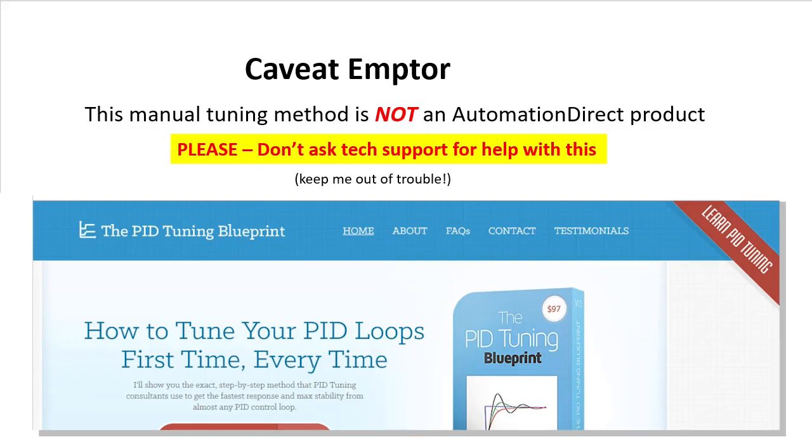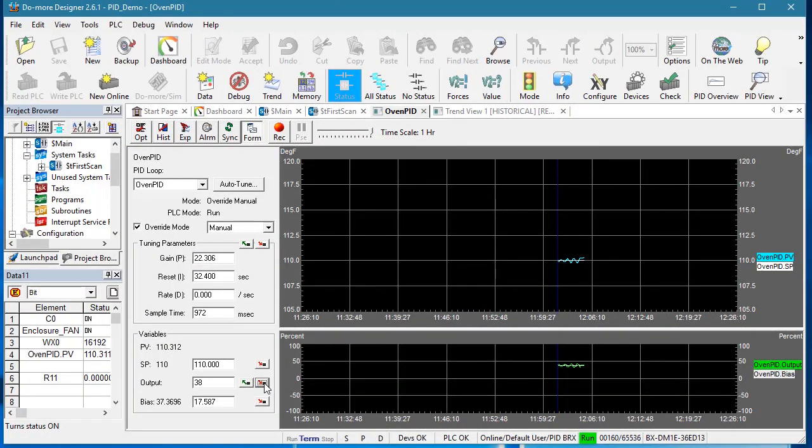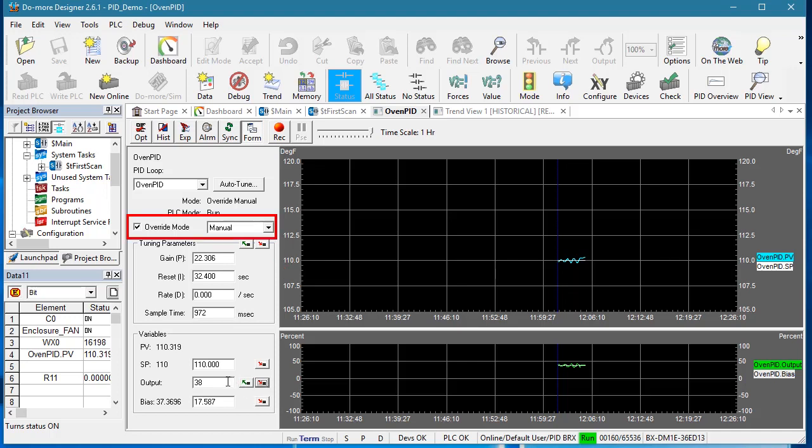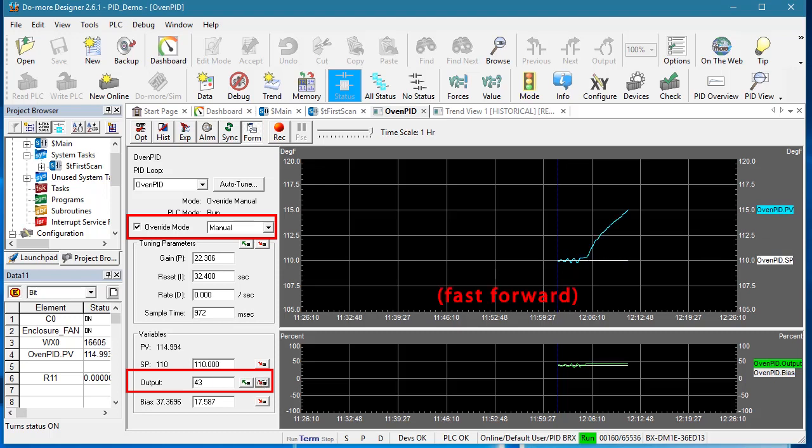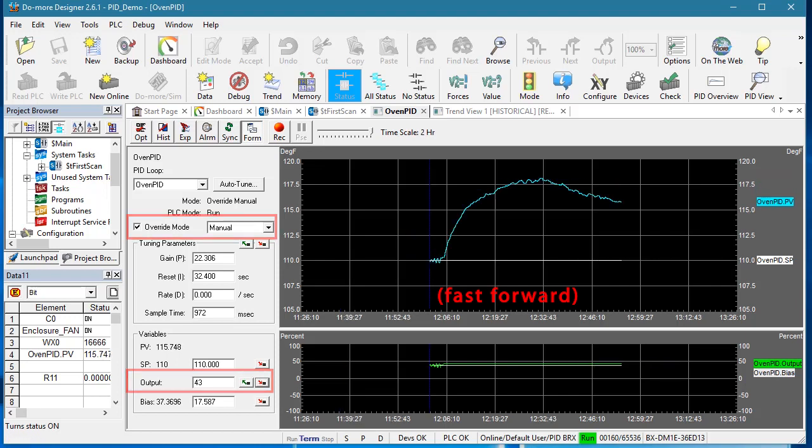Okay, let's do it. Just like in the previous video where we set up the PID process simulator, we need to get our system stable – near the 110 degrees we want to operate around – then manually bump the PID output a few percent. I'll do 5 percent. You'll want to do some small amount that's enough to get your system to respond and that represents the kind of process changes you expect.